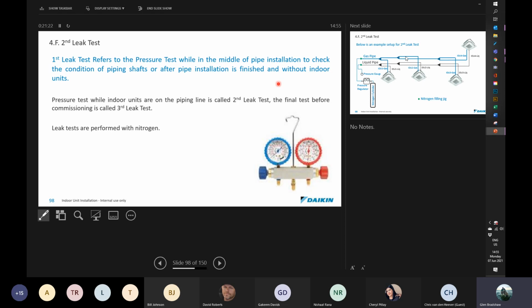If you try and do the pressure test at the end, when you've got a system supplying 3 floors of air conditioning and another 5 floors of vertical riser and a condenser that's meters away, suddenly you're looking at a lot of piping to try and find a leak in. And sometimes you're only looking for a leak that's like a pinhole. And it can take months to try and find leaks like that. So try and pressure test in stages.